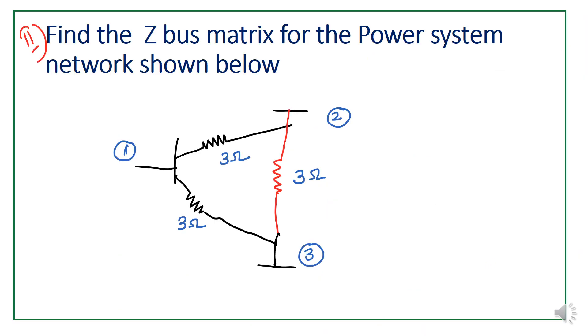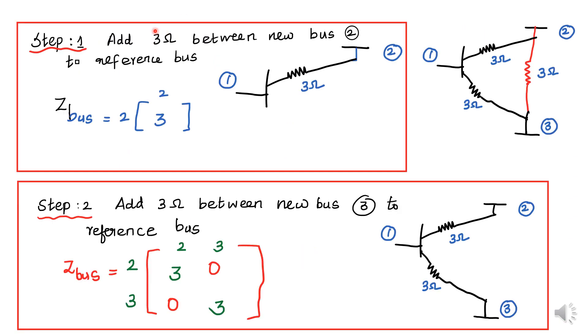Next, I am going to explain problem number 2: Find the Z-bus for the power system network shown below. This consists of 3 buses. Bus number 1 is considered as the reference bus. Remaining buses are 2 and 3, corresponding to 2 buses. The Z-bus is a 2x2 matrix. Step number 1: Add 3 ohm between new bus 2 and reference bus 1. The Z-bus equals 3 — only one element.